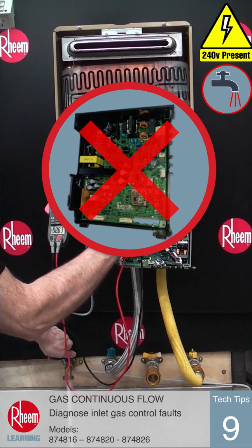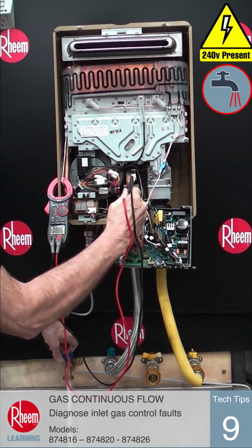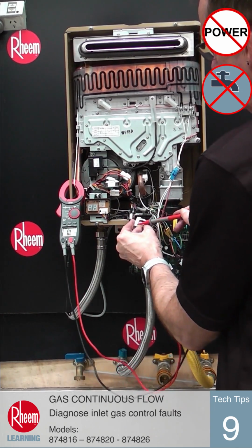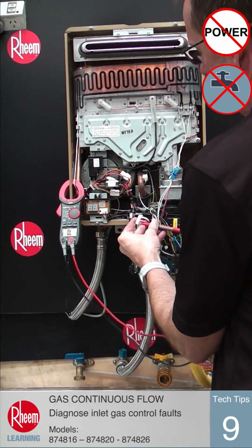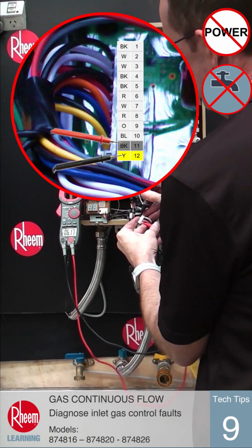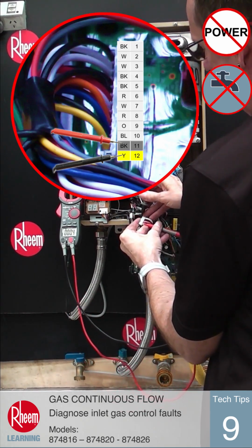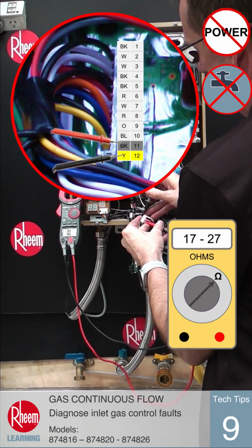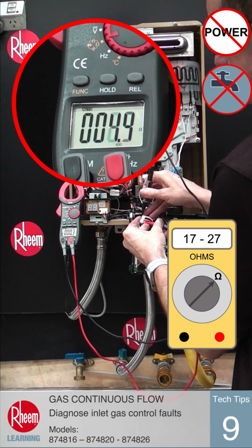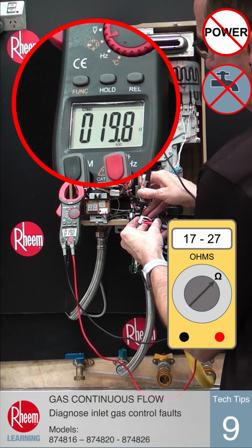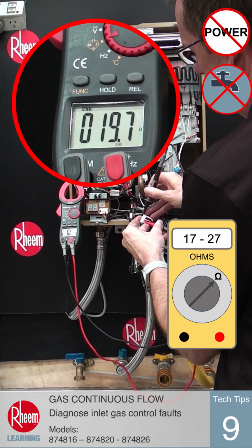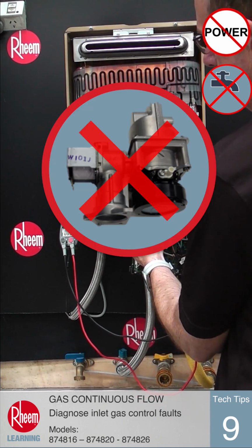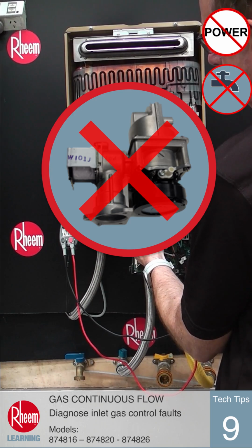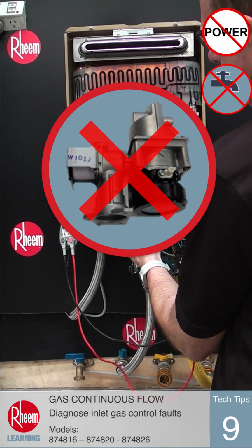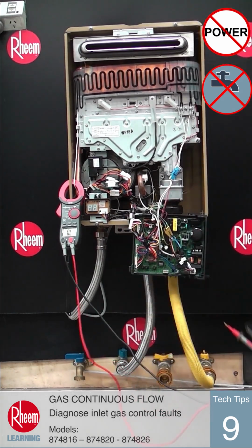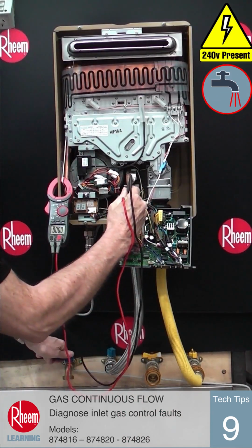If there is voltage in the correct range, turn off mains power and disconnect the plug at connector I on the PCB. And use a test meter set to ohms to measure between pin 11 black and pin 12 yellow. The reading should be between 17 and 27 ohms. If the reading is not correct, the inlet solenoid is faulty and the gas valve assembly should be replaced. If the reading is correct, the proportional gas flow regulator should be tested next.